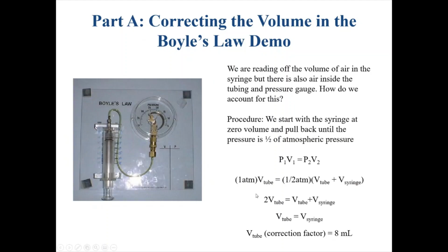So one thing that we have to correct for is the volume of the gas inside the tubing. As you change the volume in the syringe, we can measure that directly, meaning we can see, reading off the numbers, where we are in terms of volume. The problem, though, is we don't know what the volume is of the air inside this tubing. So there's actually a very simple procedure we can do that allows us to get the volume inside of the tubing. And this actually relies on P1V1 equals P2V2, or Boyle's law.